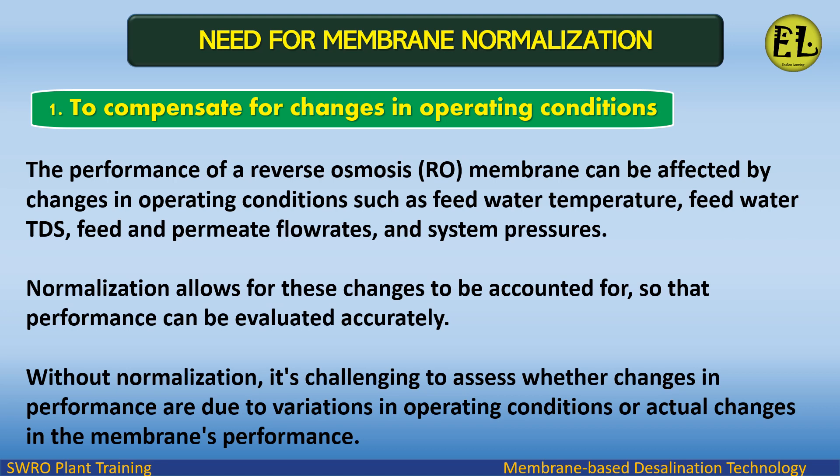Most membrane manufacturers and a few OEMs have developed software programs to normalize operating data. Without normalization, it's challenging to assess whether changes in performance are due to variations in operating conditions or actual changes in the membrane's performance.